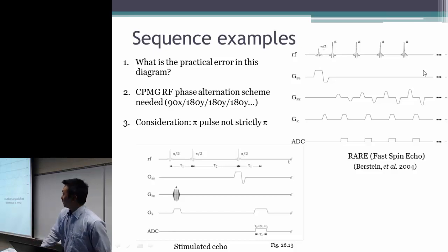But for the pi pulse, due to the failure of the Bloch equation, right? If we just simply use a sinc pulse and increase the B1 field, actually it will not reach an exact 180-degree pulse. Usually it can be a little bit off.